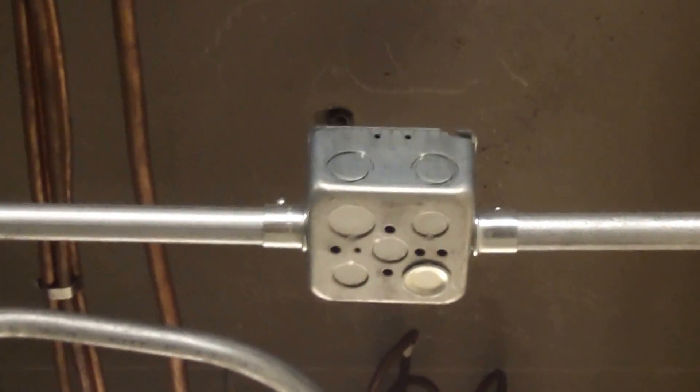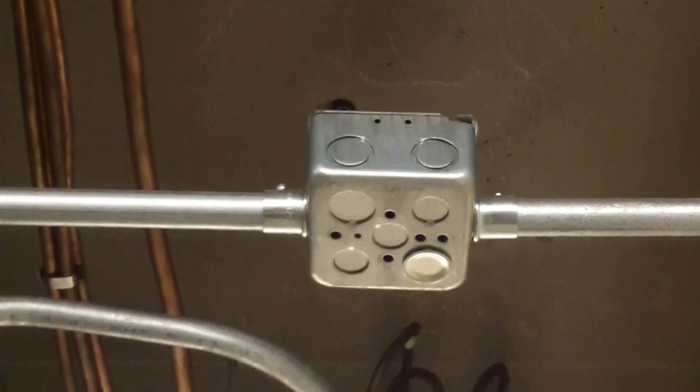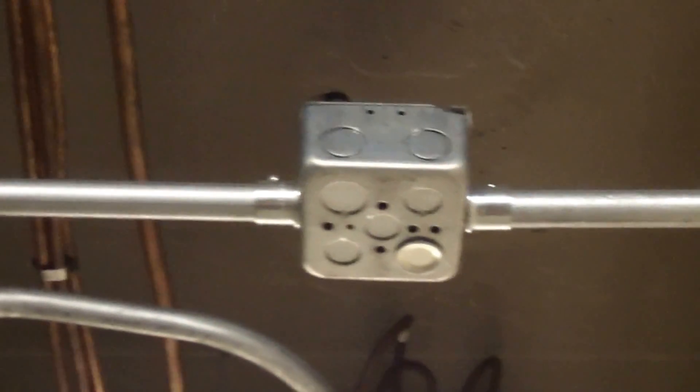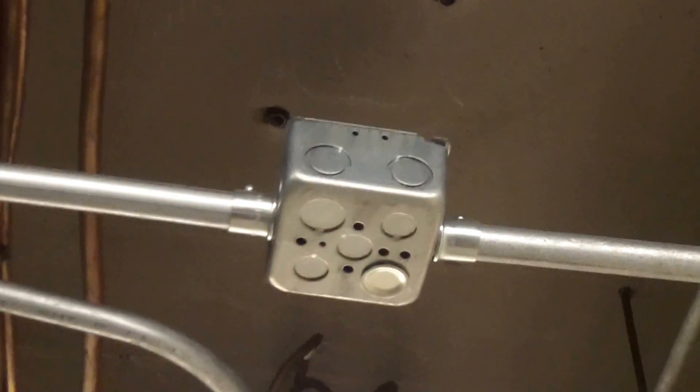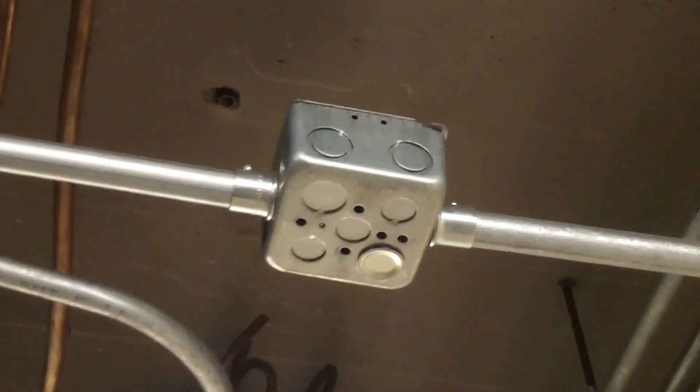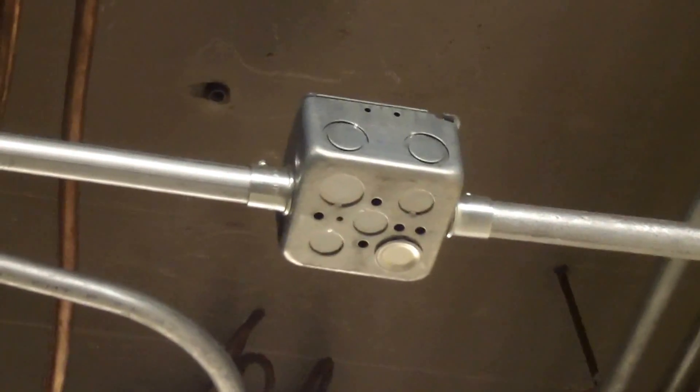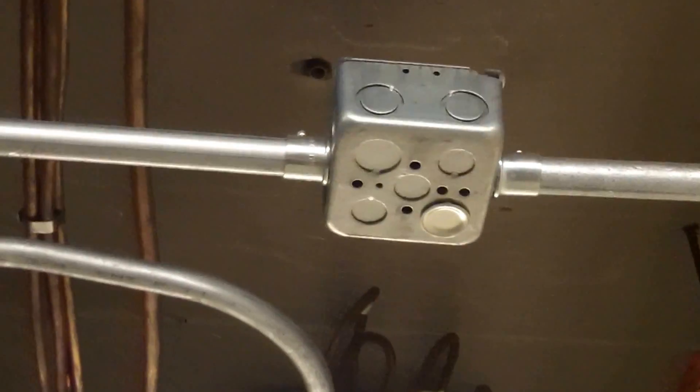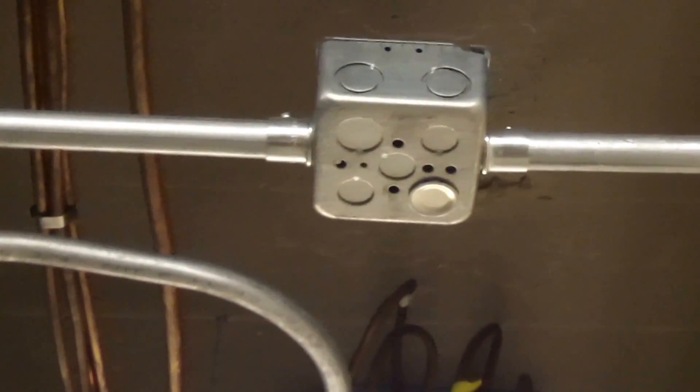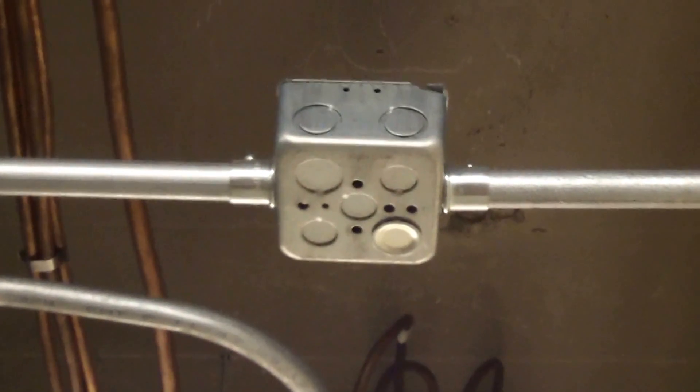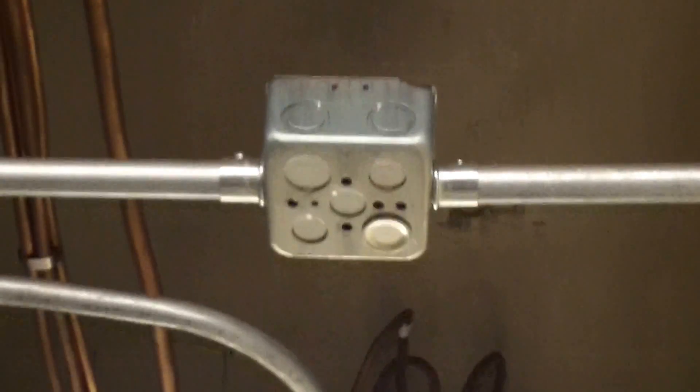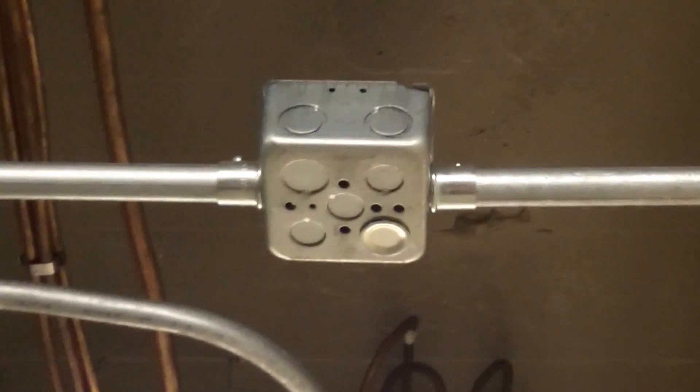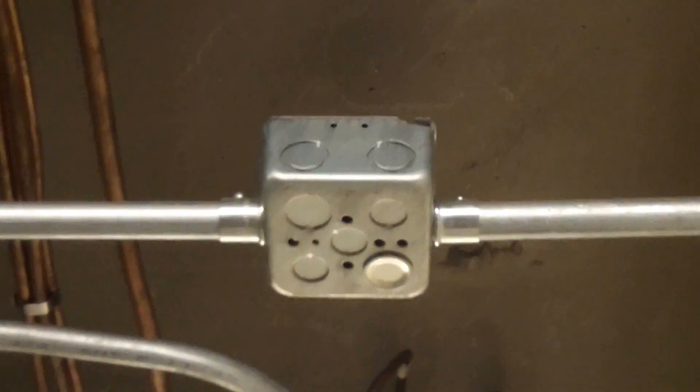This box that we see here is not properly supported. It appears to be just floating in the air. The only thing holding it up is two EMTs and the EMT connectors that are attached to the box. That's not permitted.